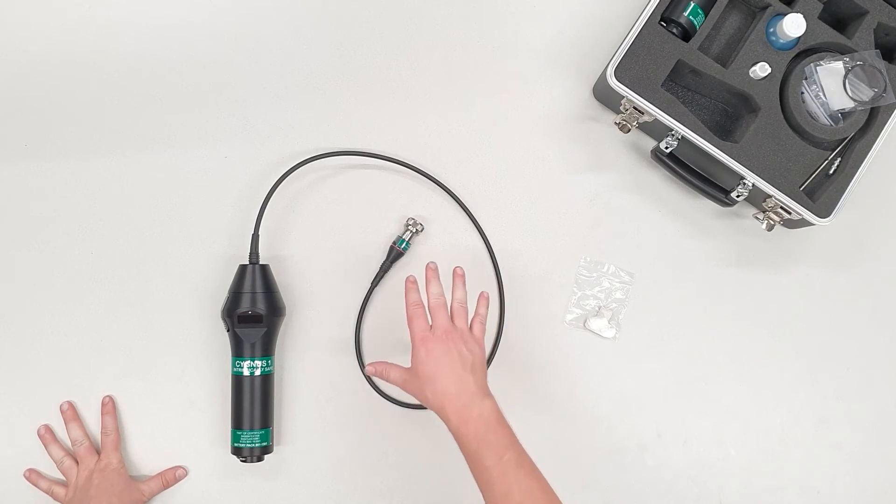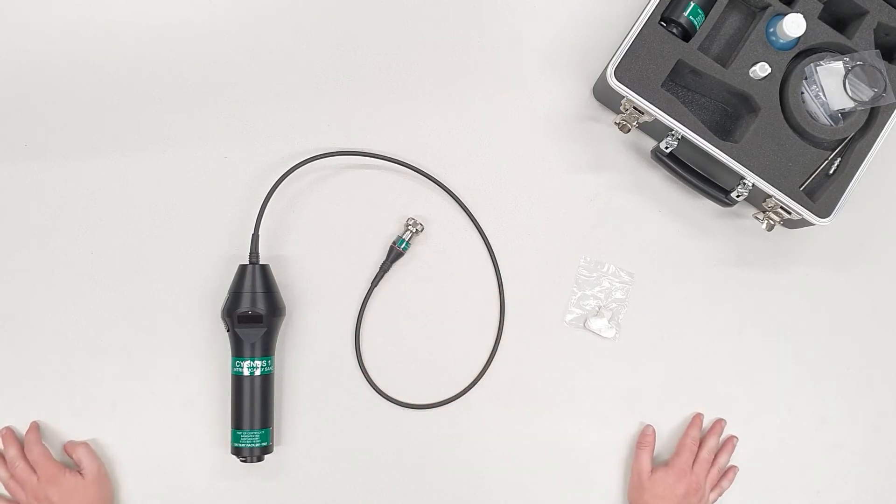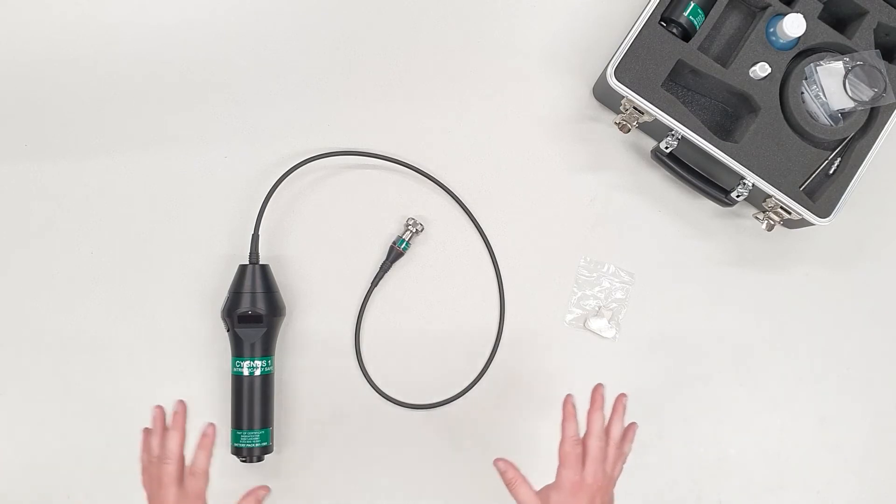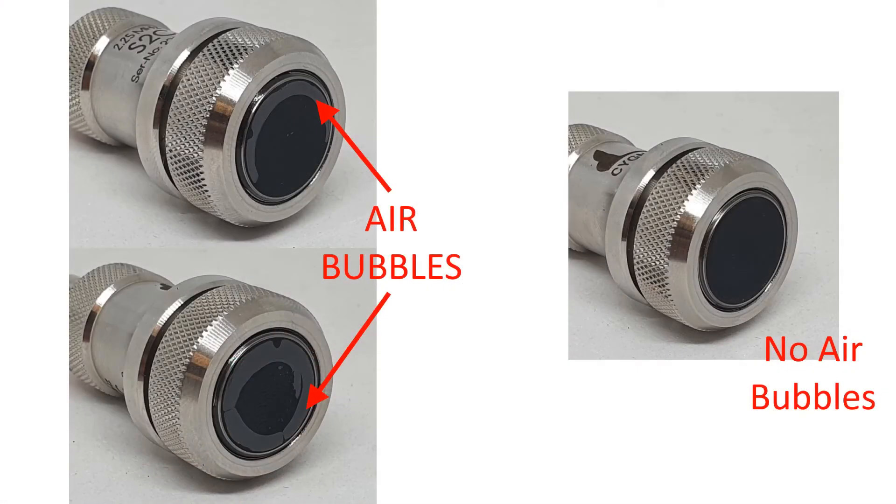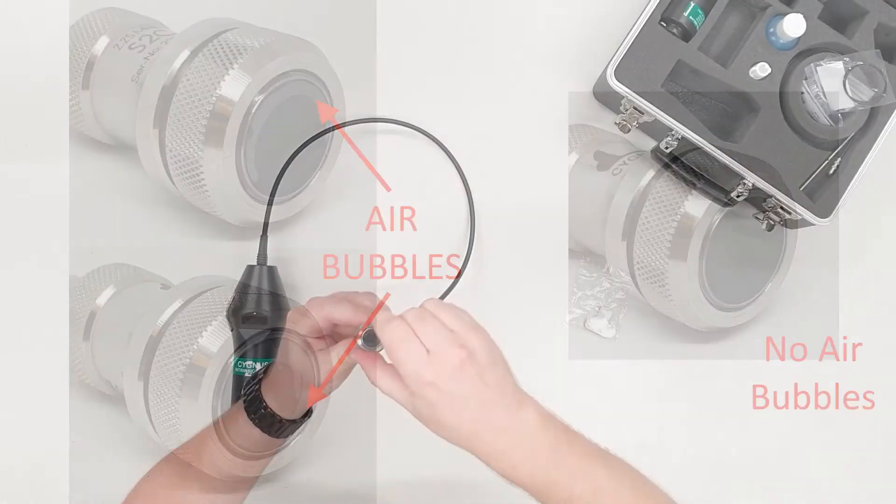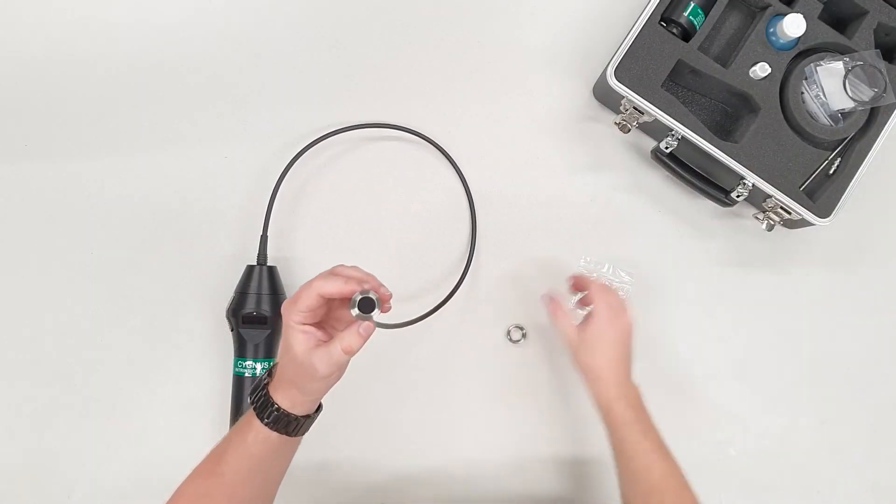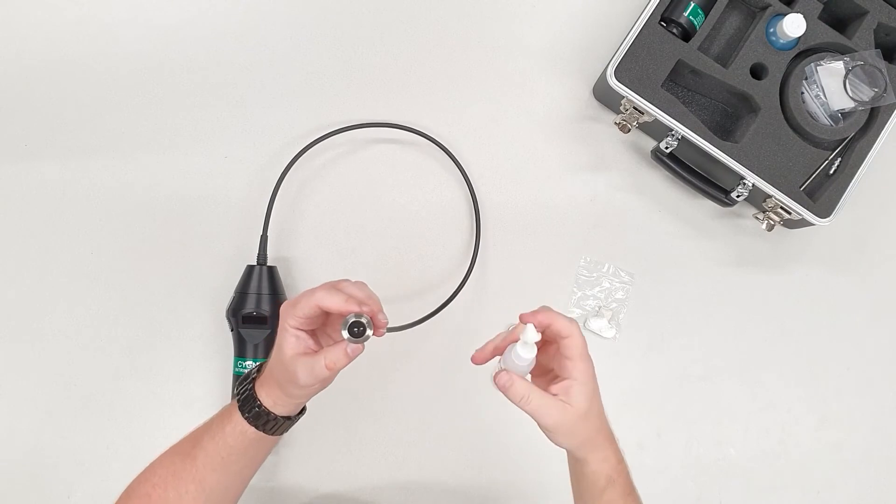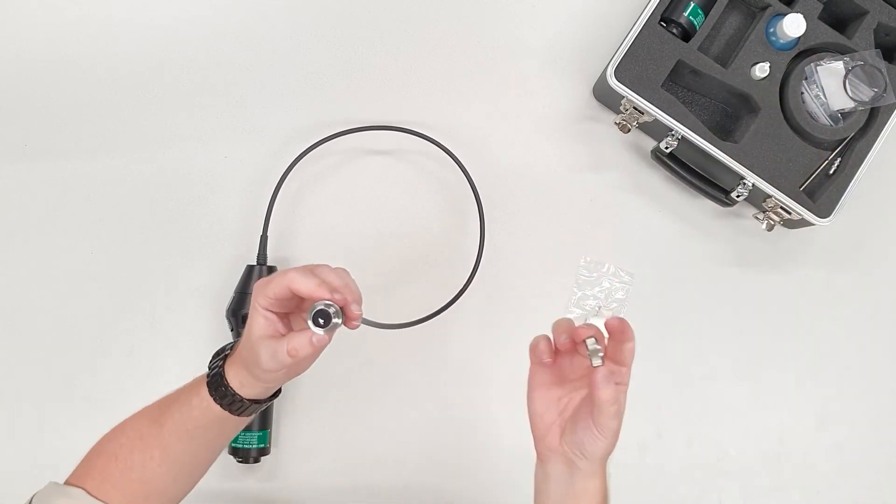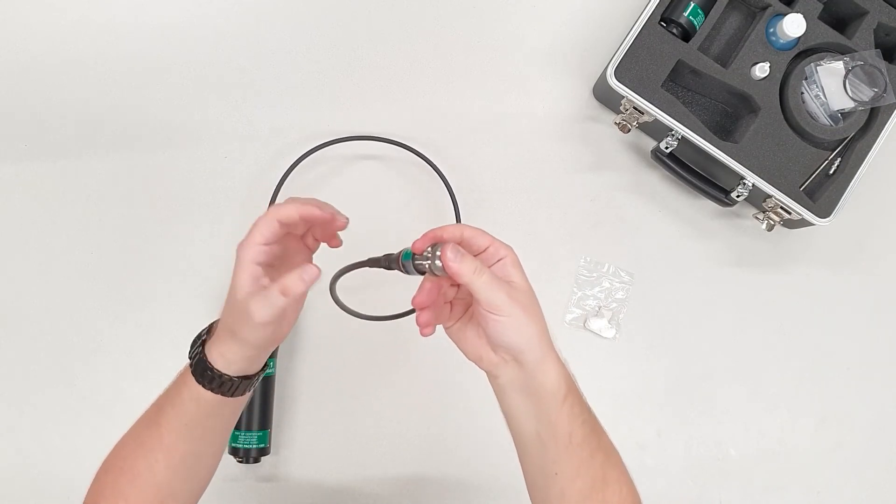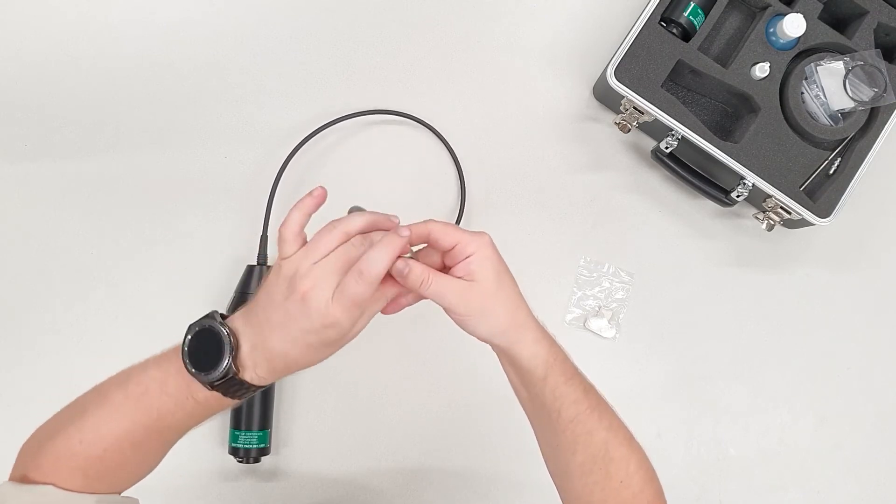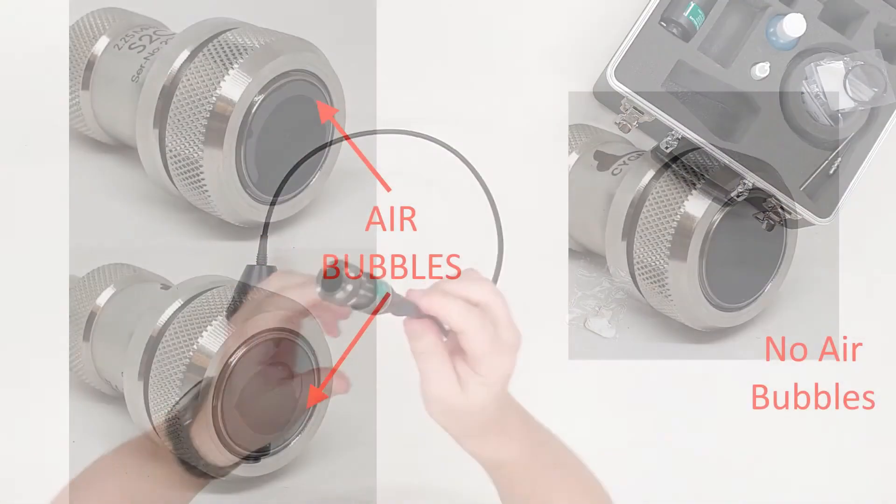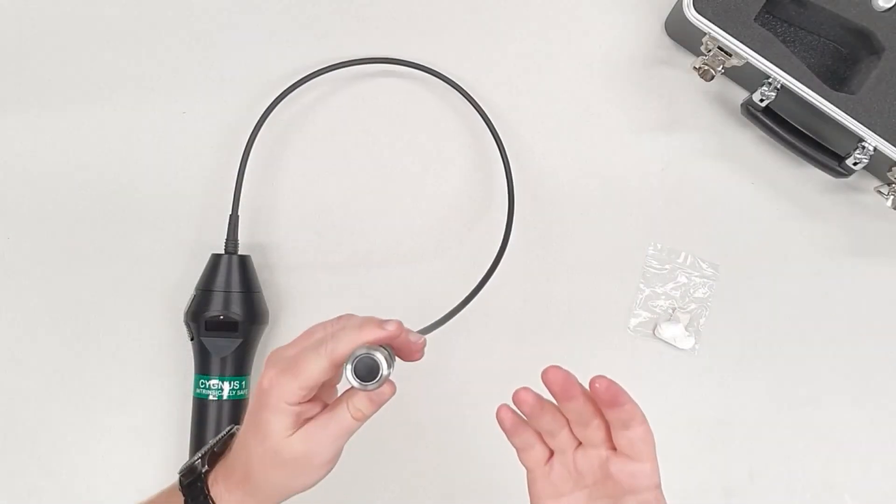It's very important to have the membrane fitted properly. Probably 95% of the time I get a call saying a Cygnus unit isn't working, the unit's fine, they just haven't installed the membrane properly. It probably means there's air trapped underneath it. As you can see in these images, there are lighter and darker sections under the membrane. It should all be dark. The lighter sections are where there's air trapped. So all you've got to do is take it off, make sure there's some membrane couplant underneath, just a drop or two on the surface. Put the membrane back on. When you put it on, put your thumb over the surface and squeeze, then tighten it up. That will squeeze all the air out from underneath, and you'll have a nice clean surface without any air bubbles.